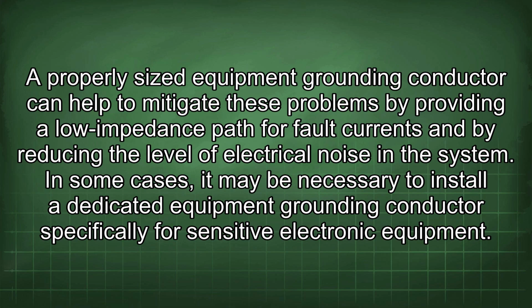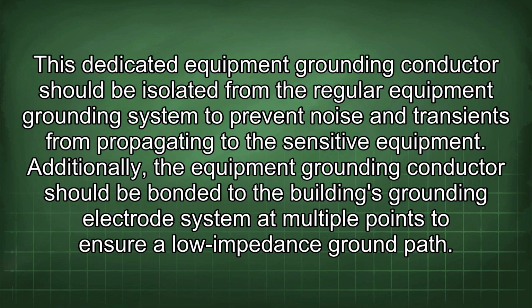A properly sized equipment grounding conductor can help to mitigate these problems by providing a low impedance path for fault currents and by reducing the level of electrical noise in the system. In some cases, it may be necessary to install a dedicated equipment grounding conductor specifically for sensitive electronic equipment. This dedicated equipment grounding conductor should be isolated from the regular equipment grounding system to prevent noise and transients from propagating to the sensitive equipment.